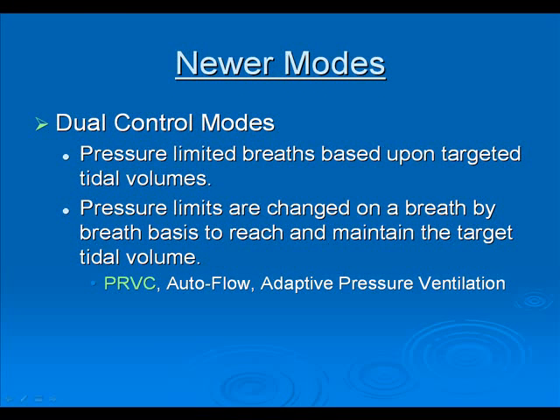Newer modes are referred to as dual control modes. We can have pressure-limited breaths based on targeted tidal volumes, where those pressure limits are changed on a breath-by-breath basis to reach and maintain the targeted tidal volume. Modes such as PRVC, autoflow, or adaptive pressure ventilation are good examples of dual control modes.